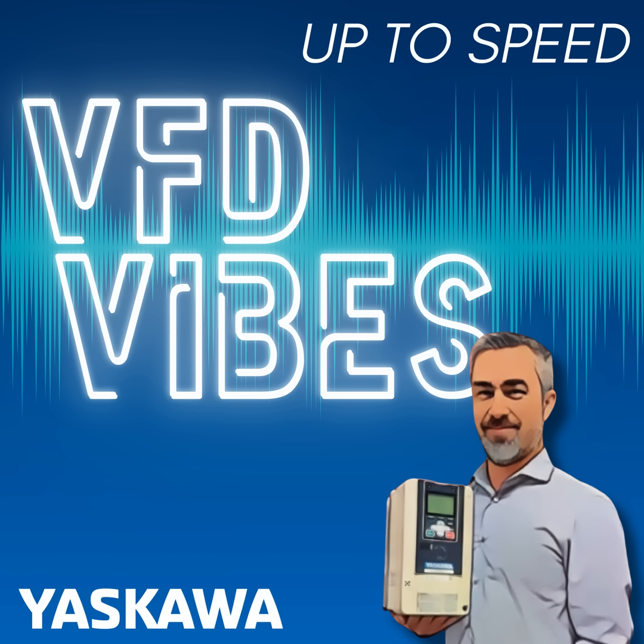Now, UL 508C products are still valid for sale and installation, but manufacturers are no longer able to introduce new products under the old standard. So you can't develop a new product now and try to get it listed under UL 508C. They won't do it. They say, nope, you've got to do the work for the new standard, 61800-5-1. I'm going to take a guess here. I'm going to call it 5-1 for short.